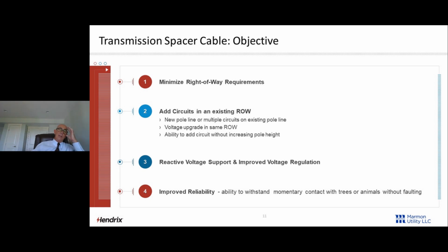Number 3, we want to have reactive voltage support and improved voltage regulation. We know that when we bring the phase conductors closer together, we're canceling out the mutual inductance. We're canceling out 15 to 20% of the impedance, and therefore the voltage at the end of the line is 15 to 20% higher. We've got a better power factor. The cap banks are switching on and off less frequently. The tap changers at the sub are banging around a lot less. So it's got all kinds of benefits there. We'll probably be able to buy less aluminum since we have improved voltage regulation. So that has a dollar figure attached to it as well.